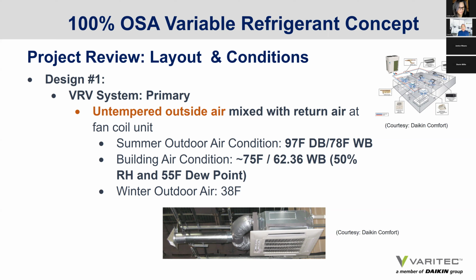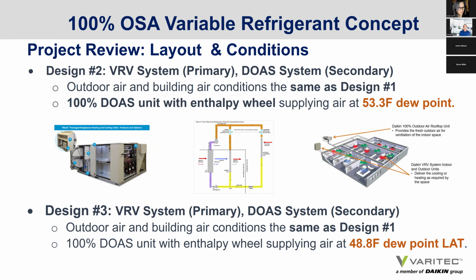We look at a building air condition of 75 degrees at 50% RH, which we could achieve certainly in our monsoon months, and a winter condition of 38 degrees. Design two, we actually used a 100% outside air solution, providing a DOAS unit that is parallel to the variable refrigerant system. But we look carefully at dew point control by providing a standard 55 degree air condition off the coil at 54 degree wet bulb, resulting in a supply air dew point of 53.3 degrees. Design system three, we designed with a low dew point DOAS supply air decision. And we're going to speak to our rather surprising findings on what that meant to the actual system.